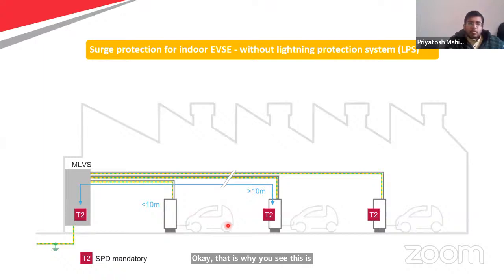Now this one again is placed here because the distance from here to here is greater than 10 meters, so you place a separate SPD on this charging station. And if you find another charging station more than 10 meters away, you use another SPD there too. That is the way of placing SPDs to protect charging stations from surges.